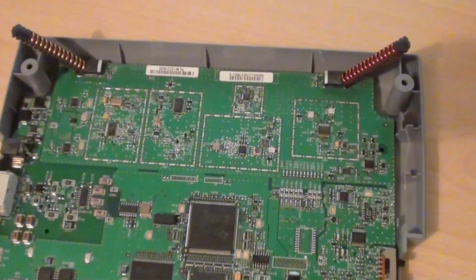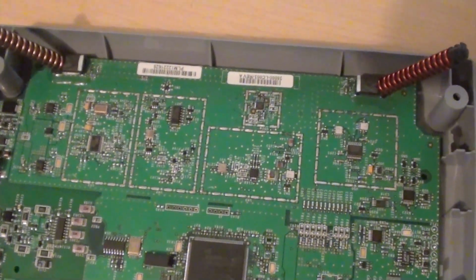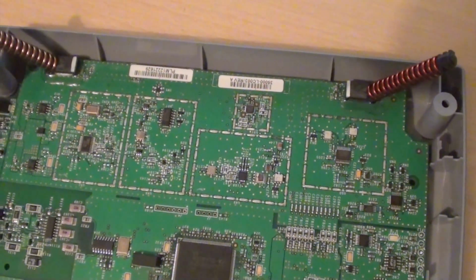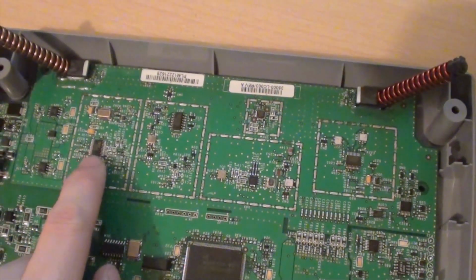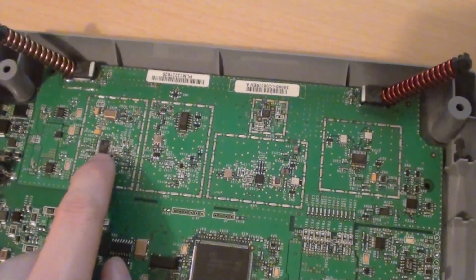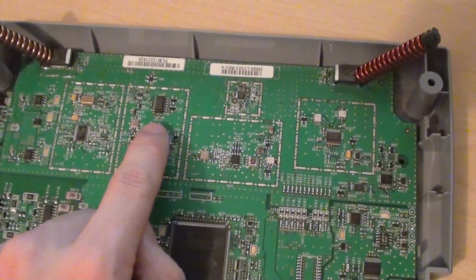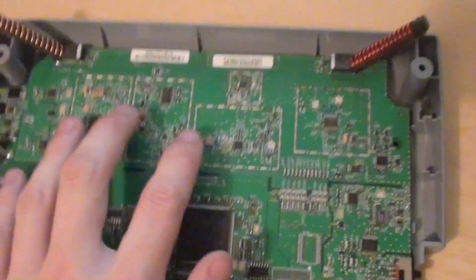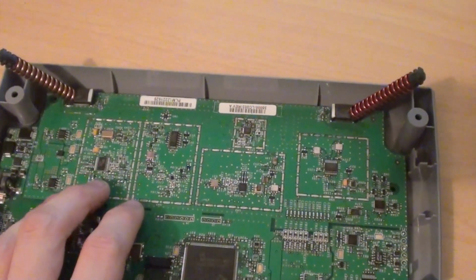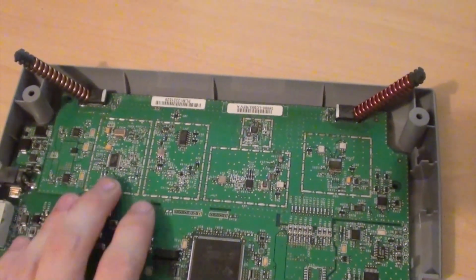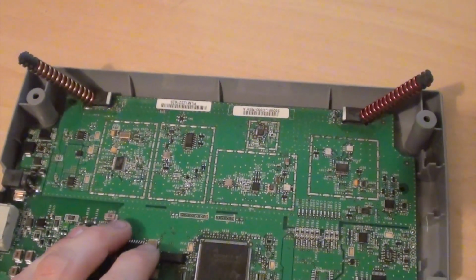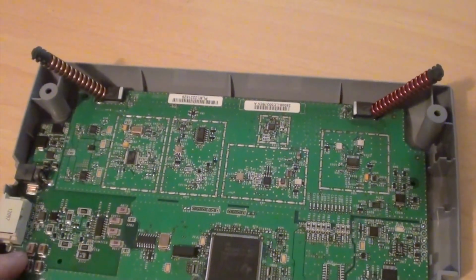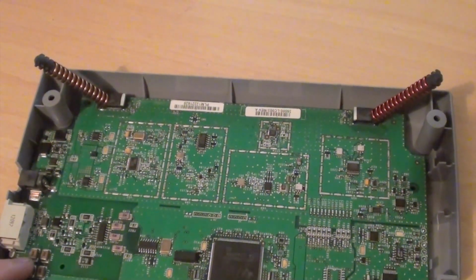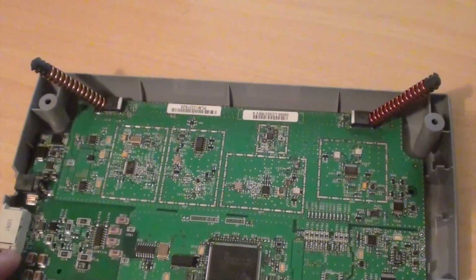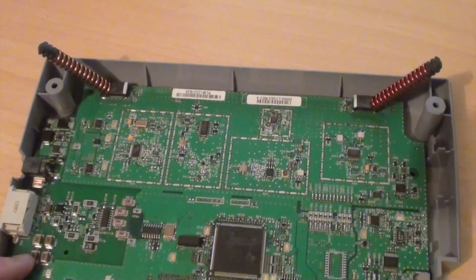Okay, well I've taken the cans off this part of the board and I didn't actually find any mobile communication ICs at all. Instead what I found was a series of these radio frequency modulation and amplification devices. So most likely what this area is for would be for maybe a different model of pacemaker or defibrillator, which doesn't actually require the paddle to be held up to the patient's chest, so it would just communicate directly with it within a certain range, say 10 feet or something like that.